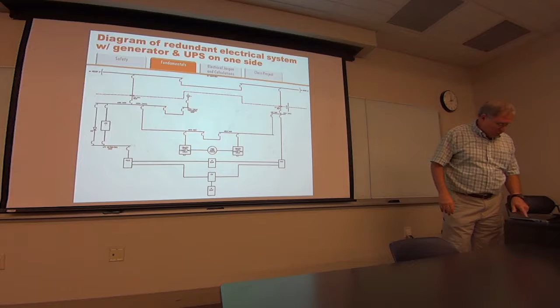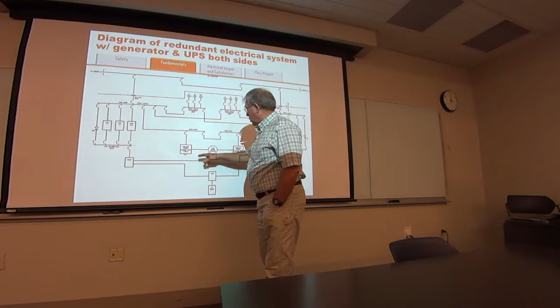It's 2N plus 1. You got N UPSs plus a spare, N generators plus a spare, and these generators can feed this way or that way. Your chillers have cold water storage, and they can be fed from either way. So if the equipment operates exactly like it's supposed to, you would probably never have a problem.